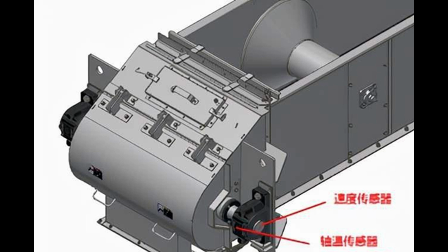7. Overtemperature automatic sprinkler protection. The thermocouple induction overtemperature sprinkler protection sensor should be fixed on the main drive drum pad, bearing seat. The simple conveyor overtemperature sprinkler protection sensor is installed on the bolt hole of the uppermost end cover on the reducer side of the main drive frame.